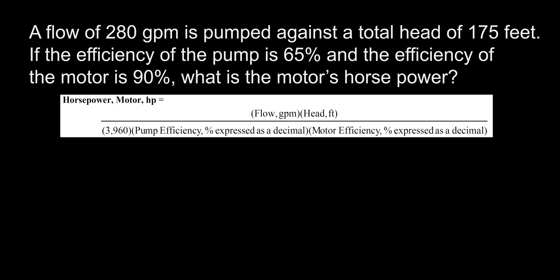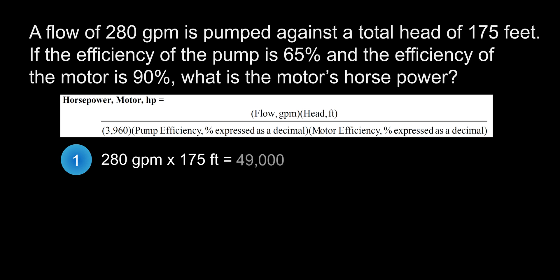Thankfully, we are given this formula for the exam. For the first step, we will solve for the top half of the formula. We will plug in 280 gallons per minute for flow and 175 feet for head, giving us 49,000. Units are not important here because we will be converting everything to horsepower.